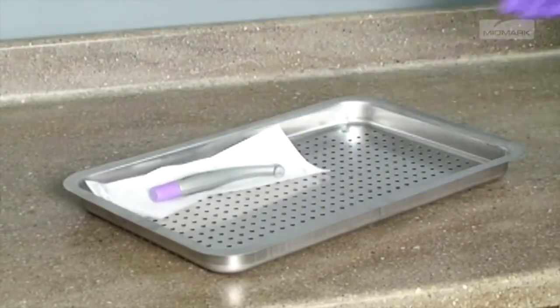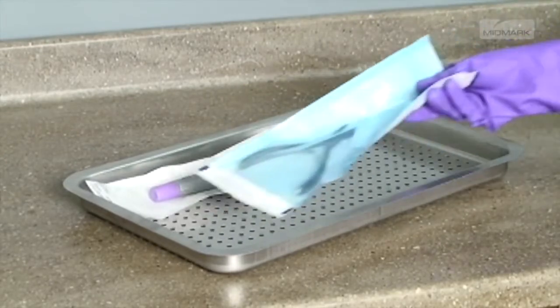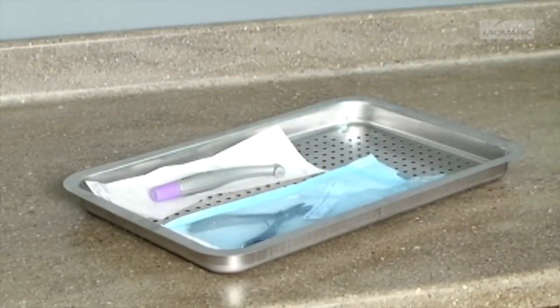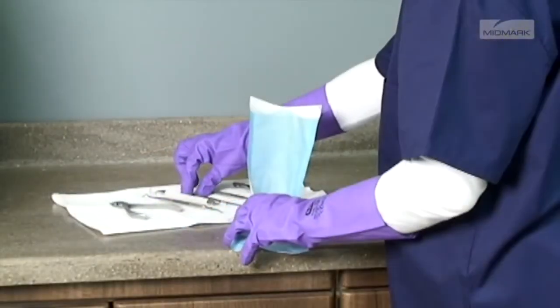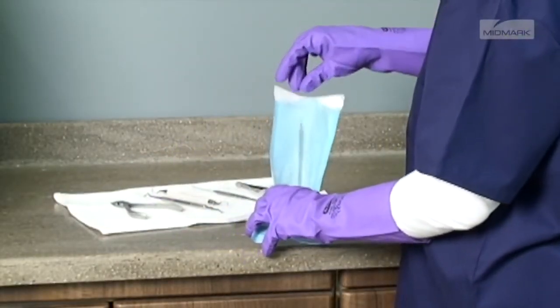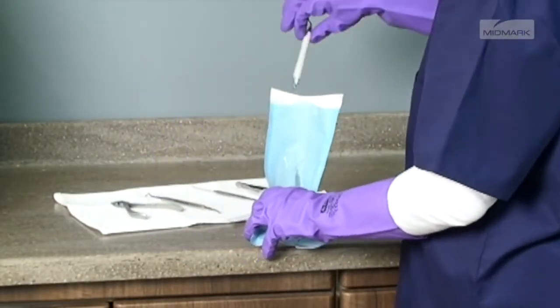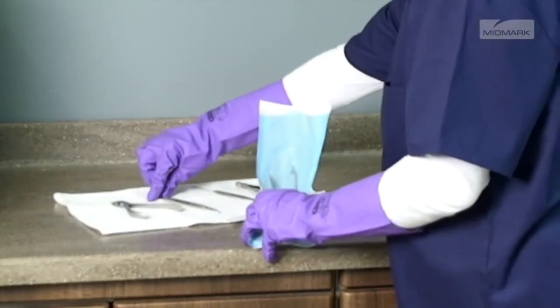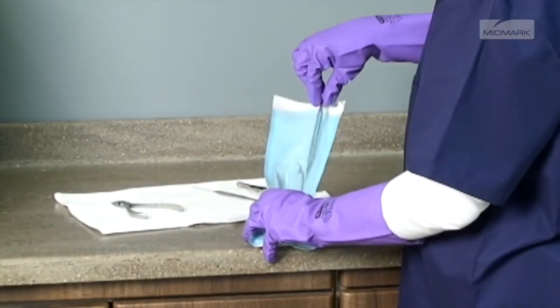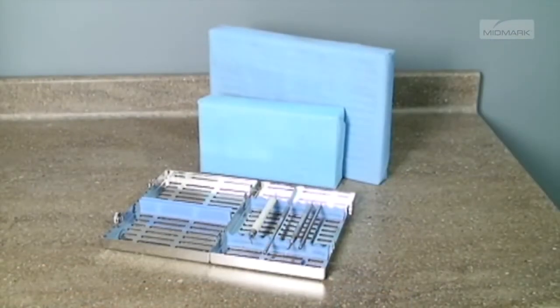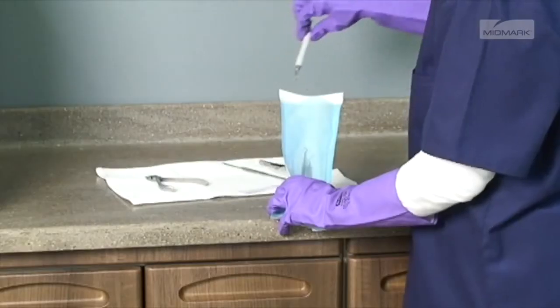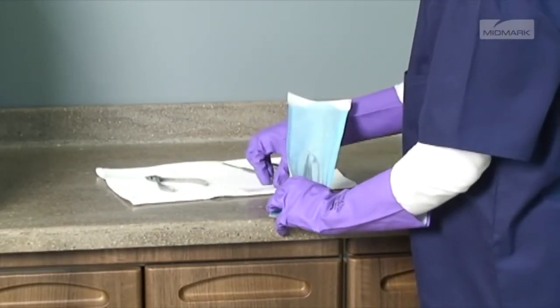The M9 and M11 are capable of sterilizing pouched or wrapped items to preserve sterility after processing. When pouching or wrapping items, use only sterilizer pouches and wraps that have been cleared by the FDA and labeled for use with the steam sterilization cycle being used. When using cassettes in the M9 or M11, follow the manufacturer's instructions for use. Do not wrap items too tightly. Sterilization can be compromised if an item is excessively wrapped. Pouched items should be loosely packed.